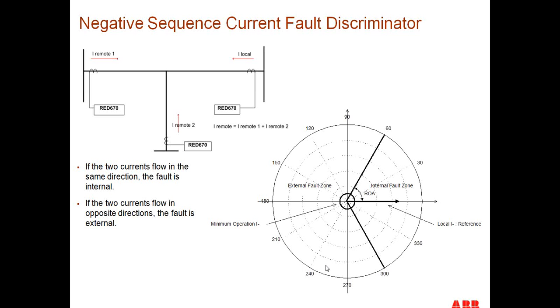But to give it a little bit of a hedge, we actually set a relay operate angle somewhere around 60 degrees or so, so that we cover 120 degrees here as an internal fault, and then over here would be an external fault. By doing this, we can set this negative sequence element to be very sensitive, much more sensitive than our normal ID minimum operate level. The ID minimum operate level may be 0.3 per unit current. This negative sequence element could be set for 0.04 per unit, 10 times more sensitive than the other element.